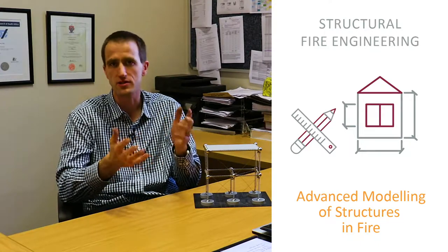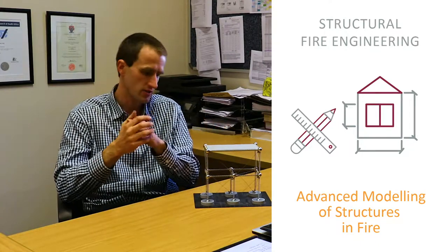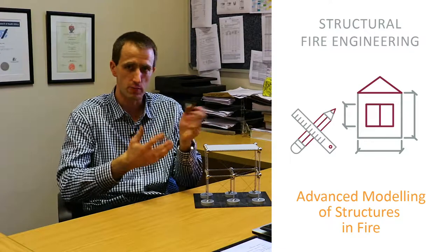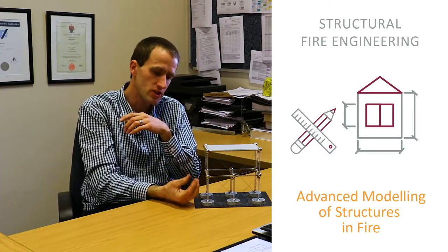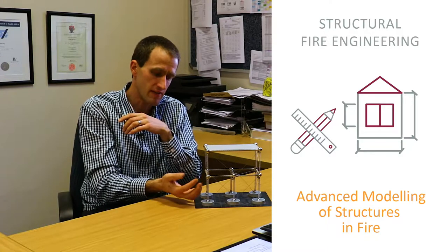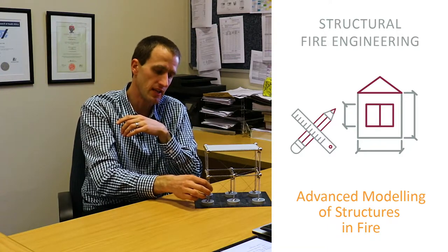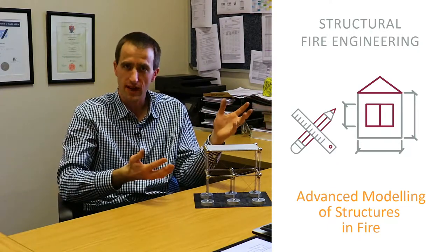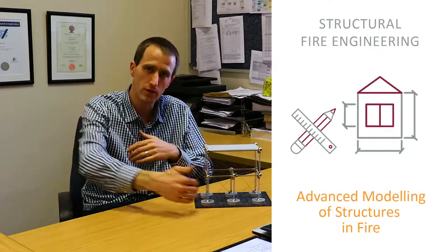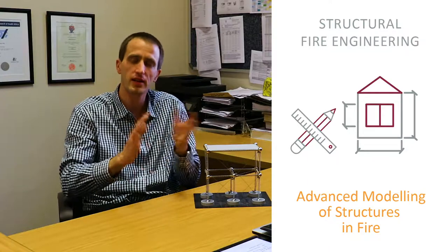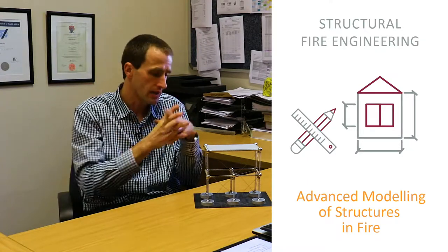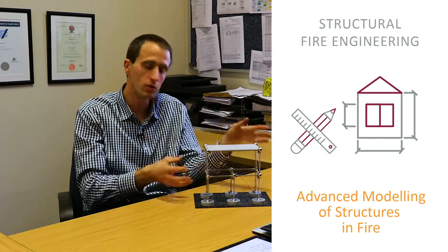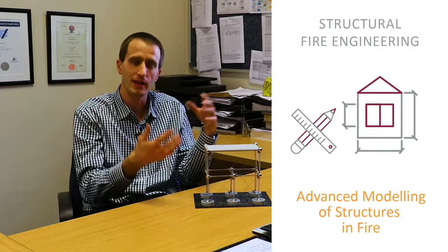There are a large variety of fire scenarios you could consider. For instance, if I was designing this structure, I could use a localized fire — especially if it's a petrochemical facility with a fuel leak — a localized fire adjacent to the structure could be quite a governing factor for design. Then I could have a traveling fire, perhaps in a large building where flashover doesn't occur, moving through the building progressively and affecting different parts at different times. I could also have computational fluid dynamic models modeling the ventilation, fuel, and other factors inside.